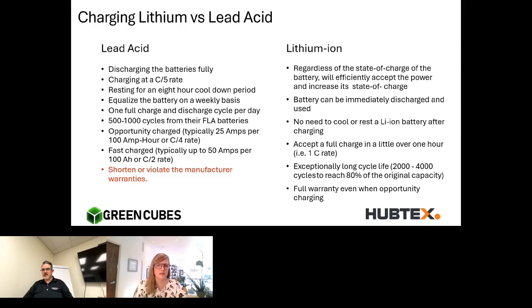With lithium ion, on the other hand, regardless of its state of charge, the battery will efficiently accept power and increase its state of charge, so it can be immediately charged and discharged. It has no need to cool because it's very efficient, so it doesn't heat up as you're charging it generally. You can accept nearly a full charge in a little over an hour, a 1C rate, and with that you can get 2,000 to 4,000 cycles down to about 80% of the original capacity, like was mentioned earlier for that application.